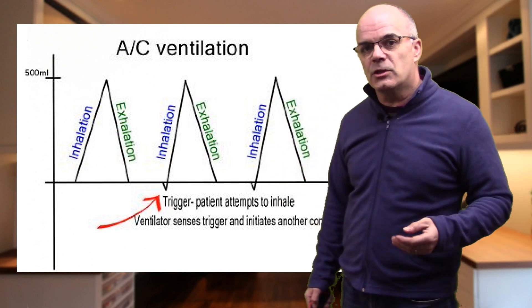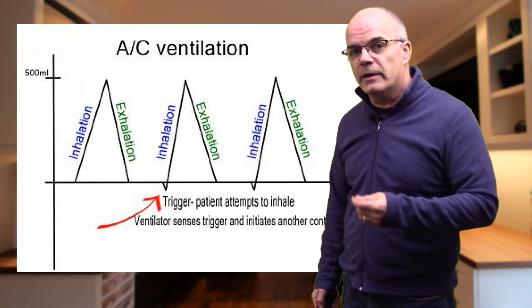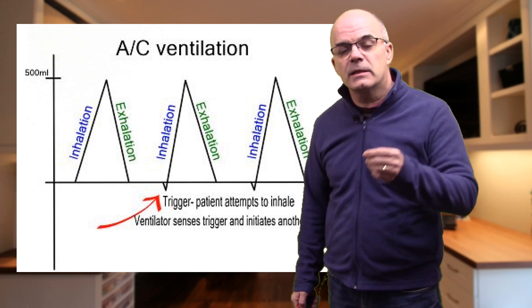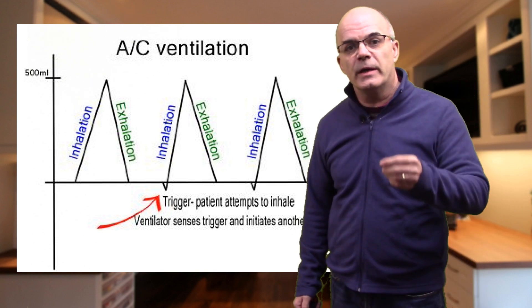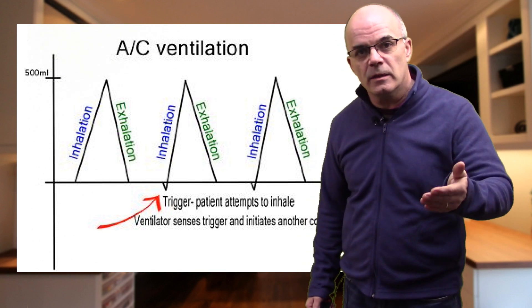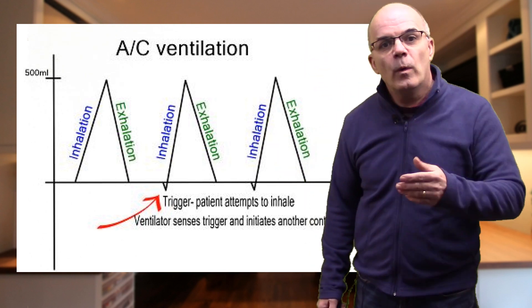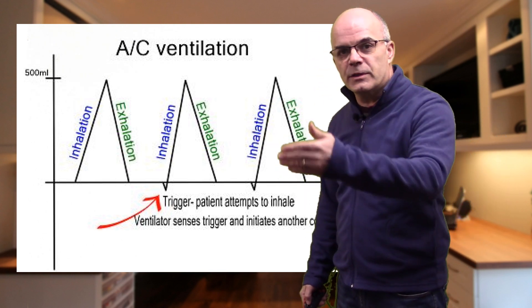The next breath is initiated by the patient. You can see the small negative flow generated by the patient. This trigger can be set to make it easier or harder for the patient to trigger their own breath, and this is often done as you start to wean the patient. The machine is set to detect this trigger and when it does, it will deliver the set volume.